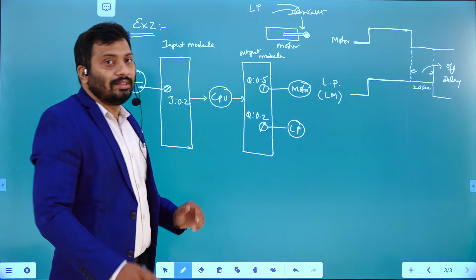Whenever this switch is going to be off, after some delay the lubricant pump needs to be off. So we need to provide some off delay. Whenever the input is there and the switch is on, both are going to be on. Whenever you turn off the input, this one needs to be off with some delay. That means after this particular motor is off, after 20 seconds the lubricant pump needs to be off. For that we need to write a program to control the motors in such a manner.